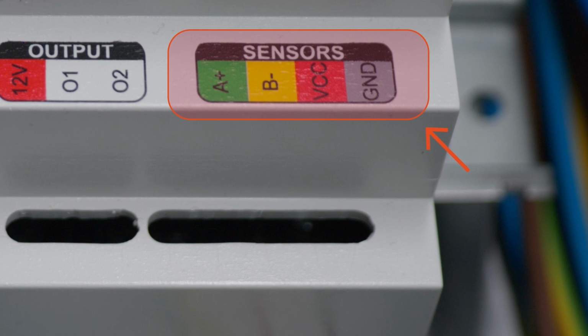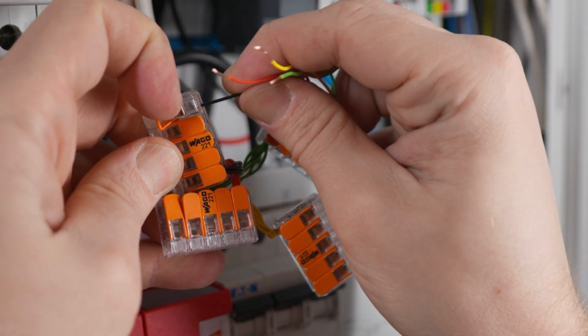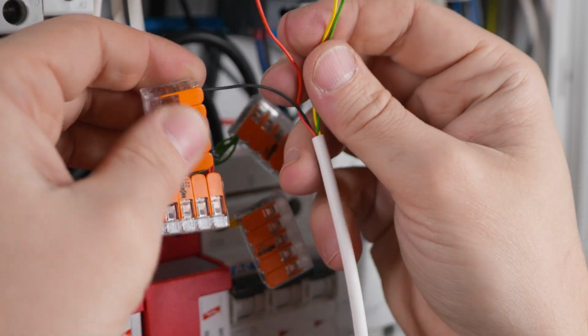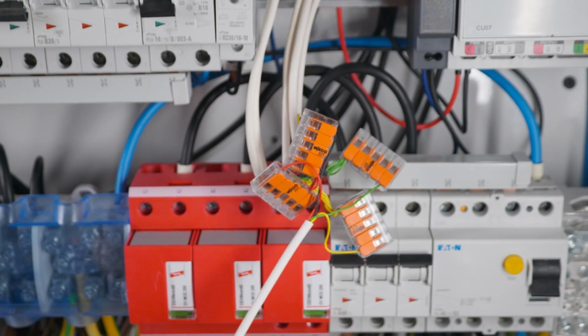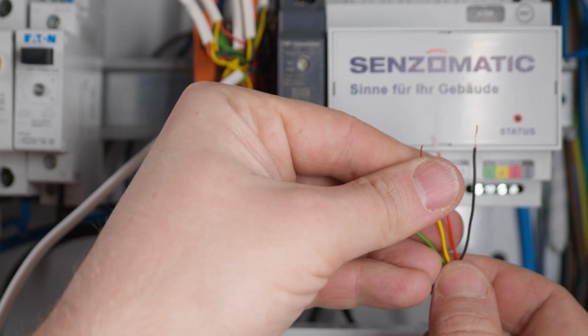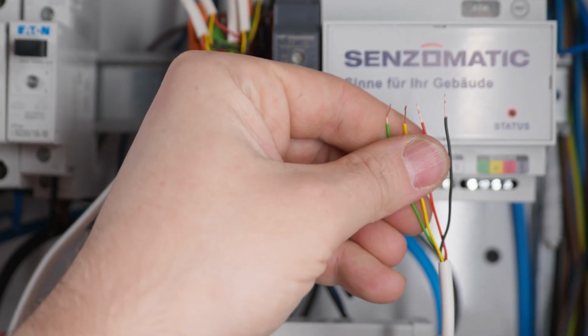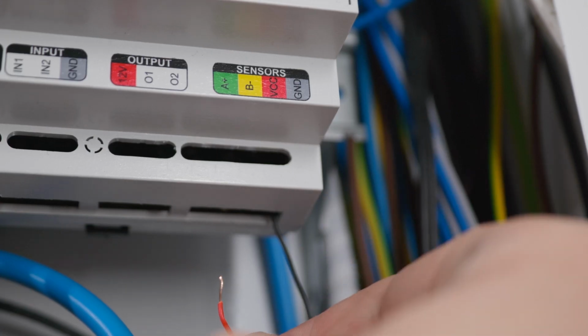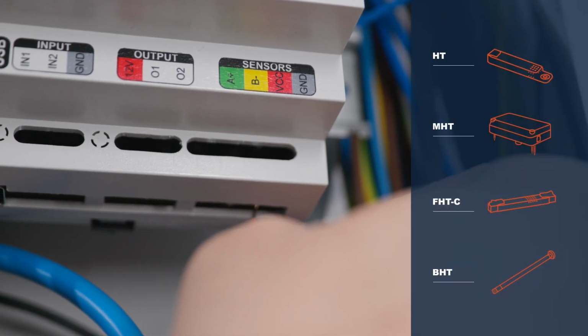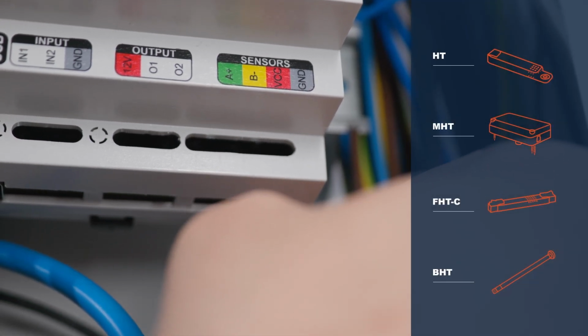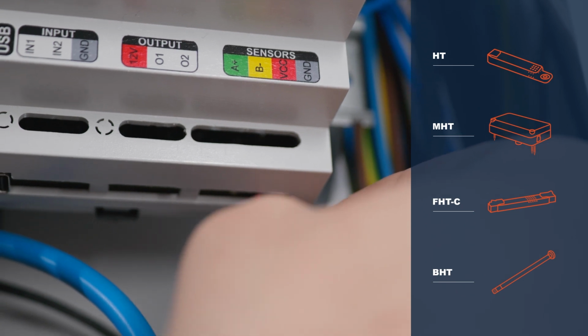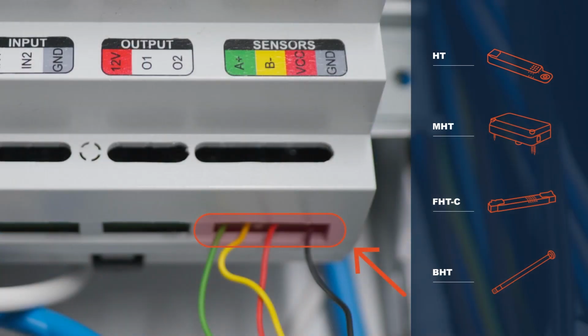Connect the sensor cables to the terminals labeled Sensors on the central unit, according to their color coding. Connect all the black, green, and yellow wires from all the sensors to their respective terminals and then route them through one cable to the terminals on the central unit. The red wires from the HT, MHT, FHT-C, and BHT sensors are connected to the terminals as well. The same process should be used for the wires of the other colors.